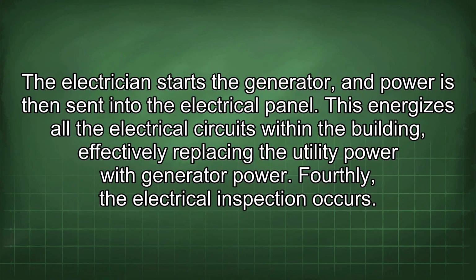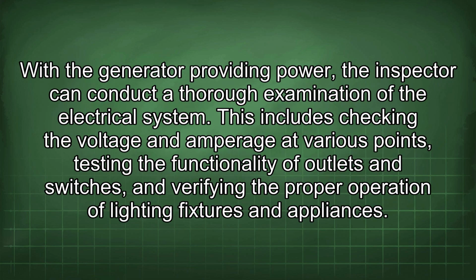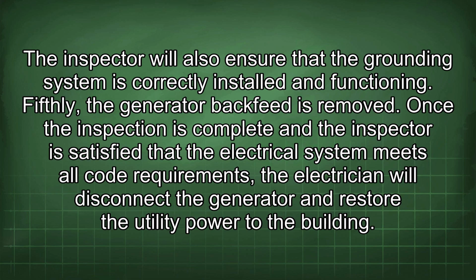Thirdly, the generator is backfed into the electrical panel. The electrician starts the generator, and power is then sent into the electrical panel. This energizes all the electrical circuits within the building, effectively replacing the utility power with generator power. Fourthly, the electrical inspection occurs. With the generator providing power, the inspector can conduct a thorough examination of the electrical system. This includes checking the voltage and amperage at various points, testing the functionality of outlets and switches, and verifying the proper operation of lighting fixtures and appliances. The inspector will also ensure that the grounding system is correctly installed and functioning.